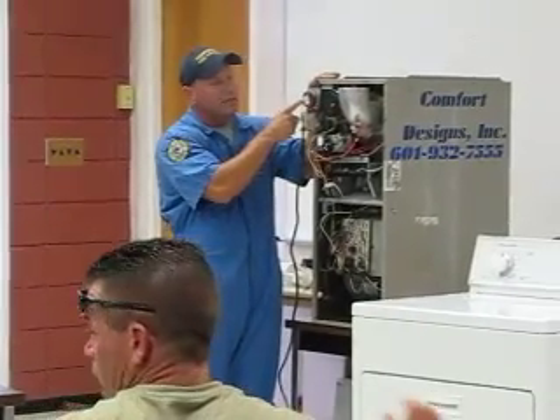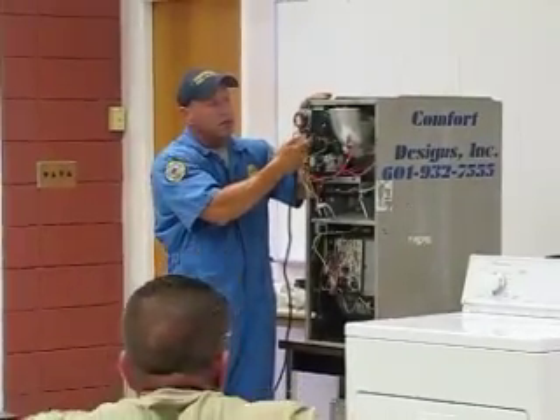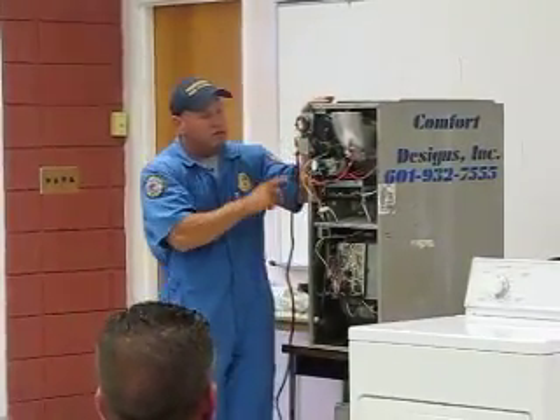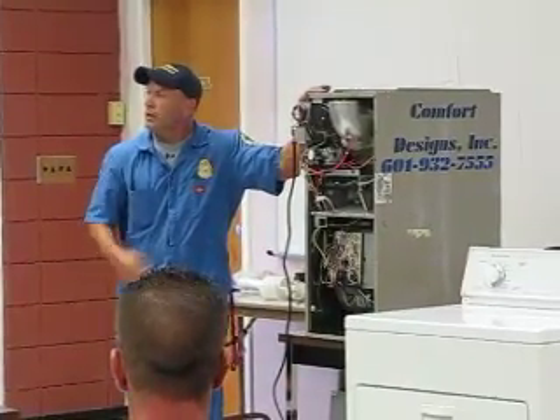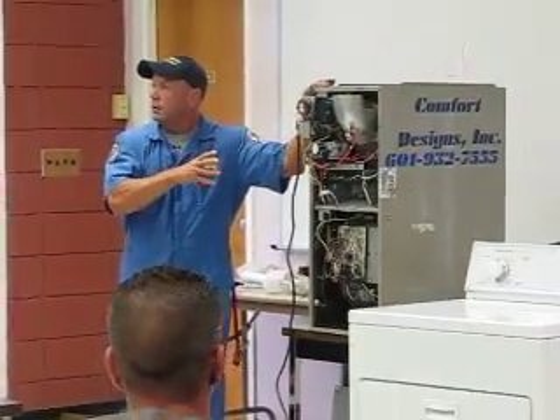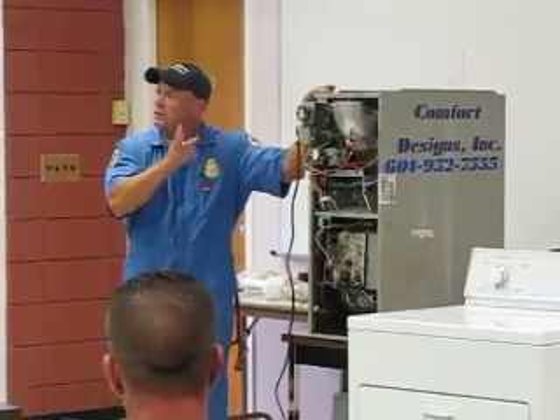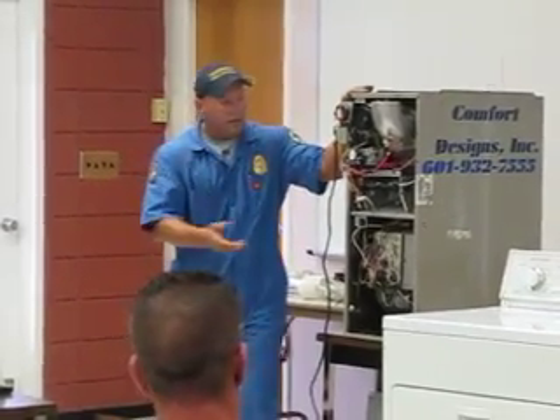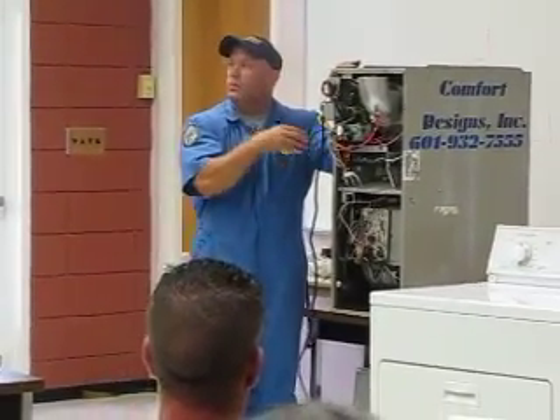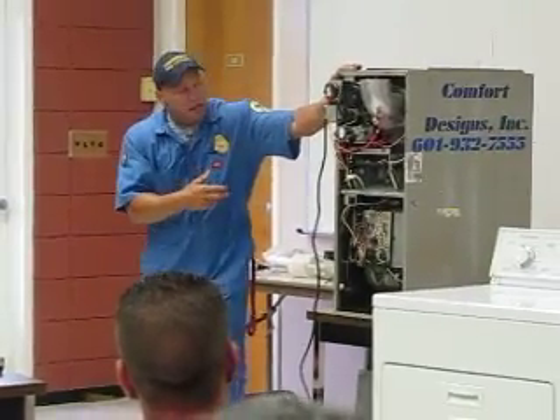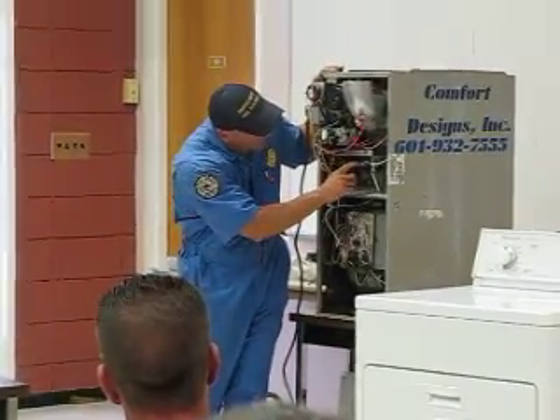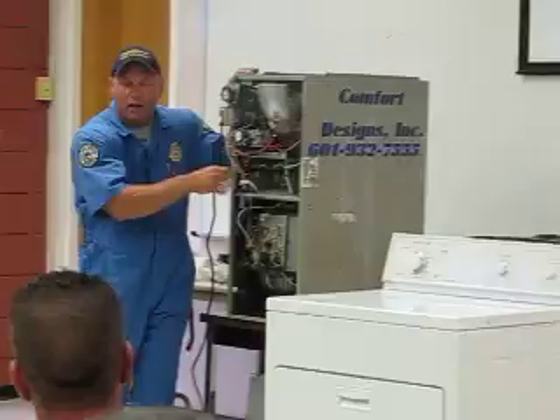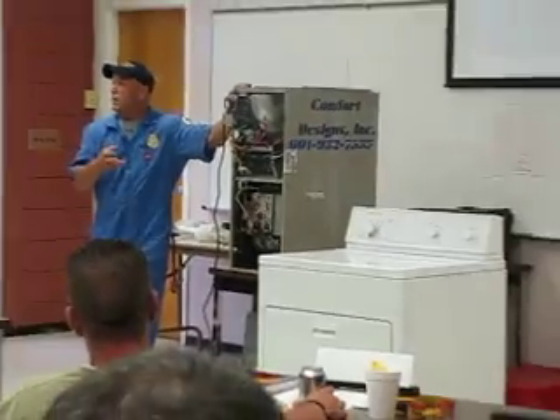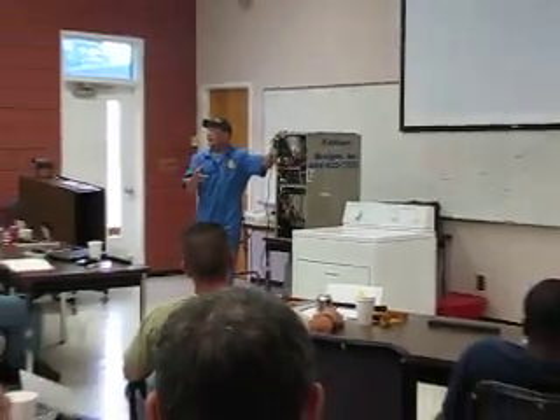It comes on, it's got a safety switch inside of it. When it comes on, it creates vacuum, it turns the safety switch on, and lets the computer know that, hey, my flue fan is working, my updraft fan is working. So once it works, it stays on for a while, then the call for heat, the gas valve will open, allow the gas to go into the system, and it's either electronically fired, which this is electronically fired, kind of like a glow plug or a spark initiator will actually ignite the gas.